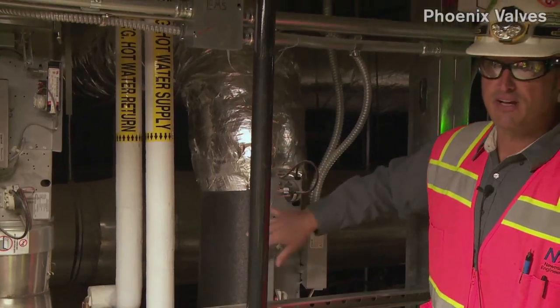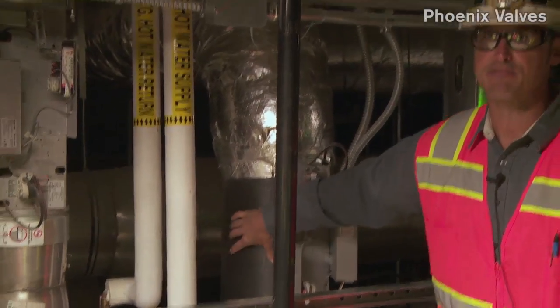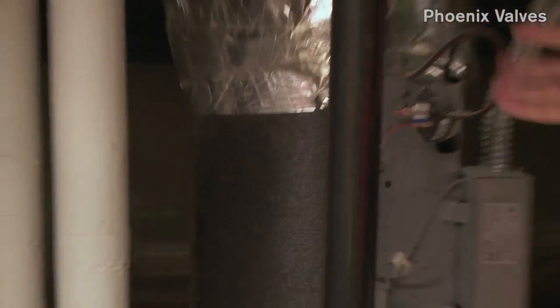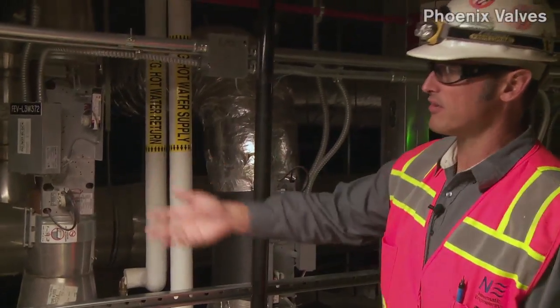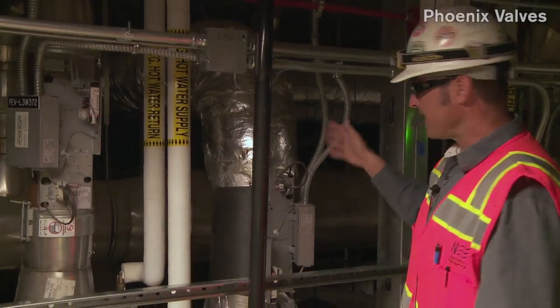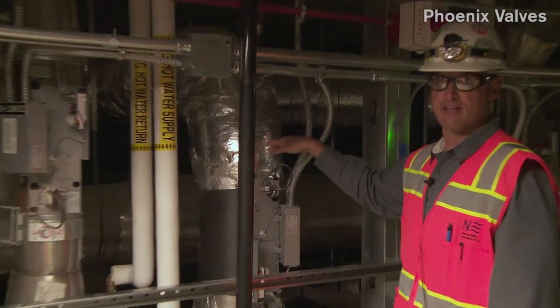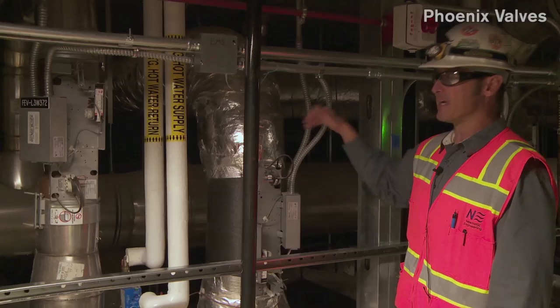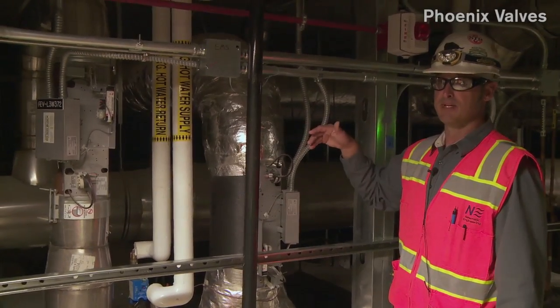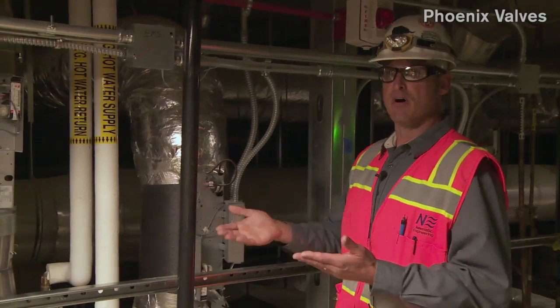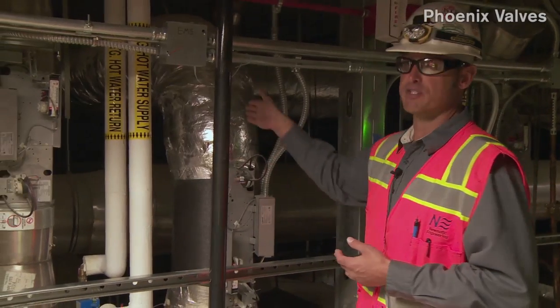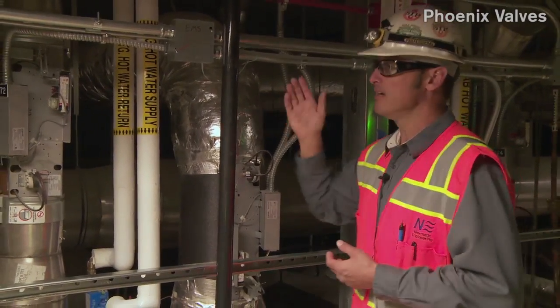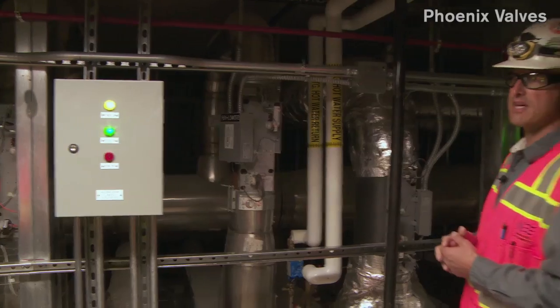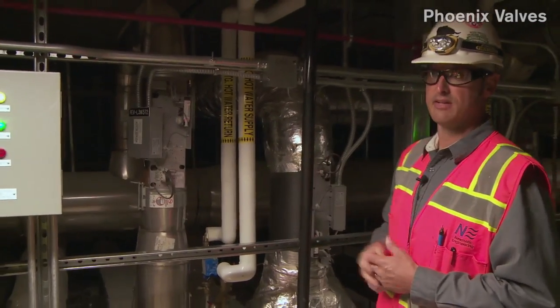And then the third valve that we have is our supply valve. You can tell it's a supply valve because it has this black foam insulation on it. That's usually how you can tell the differences in our valves, if it's general exhaust, hood, or supply. And in this building application also, it has a pressure switch. Because it's a vivarium system, you're monitoring pressures in there, so you need to know if your supply fan has enough static pressure, if your general exhaust has enough static pressure, and if the hoods have enough static pressure.